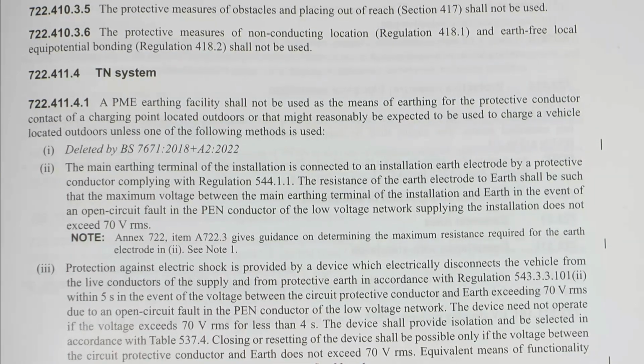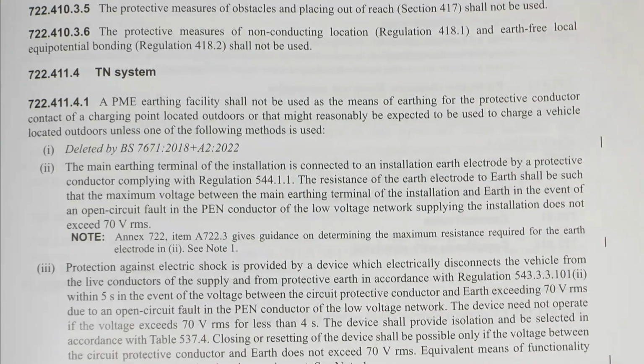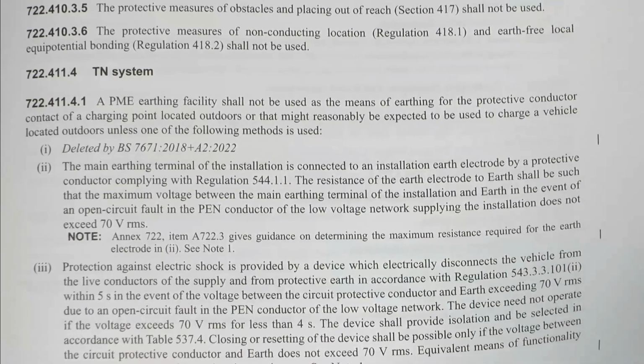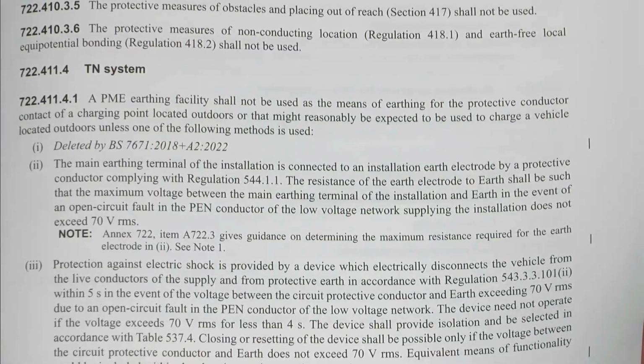In reality, nobody used it anyway, because the chance of having an installation where all the loads are perfectly balanced is pretty much zero. All you need is a single-phase lighting installation, for example, and straight away there you go. The main killer for this is that if you installed AC supply equipment for a vehicle, even though you might connect it up as three-phase, someone could plug in their single-phase car, and it would just draw the full load from one phase only, so straight away it's not balanced. In practice it was impossible. So although it's been deleted, no one really cares, because nobody used it anyway, and it wouldn't have been possible to use it even if you wanted to.